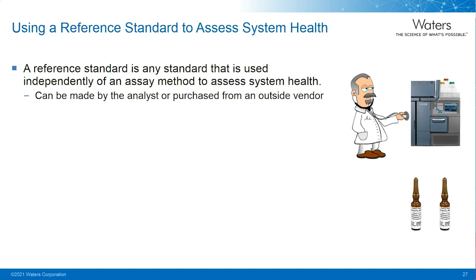So the use of a reference standard can help those analysts gain confidence in their instrument before performing method development or any other experiments. There are 3 ways to use reference standards. You can use a reference standard to benchmark. This is when you want to know that the system is in a good state, maybe after installation or performance maintenance. For qualification, you can use a standard to do routine qualification checks to confirm continued good system performance, or maybe use it when a failed qualification check would trigger troubleshooting.